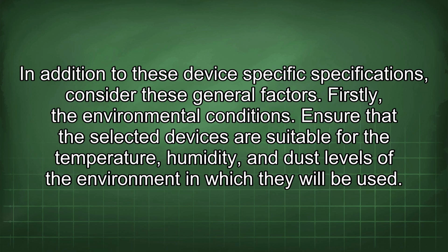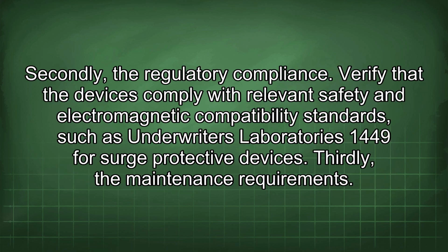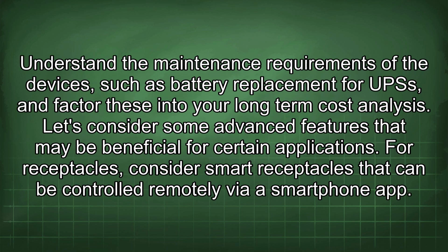Firstly, the environmental conditions. Ensure that the selected devices are suitable for the temperature, humidity, and dust levels of the environment in which they will be used. Secondly, the regulatory compliance. Verify that the devices comply with relevant safety and electromagnetic compatibility standards, such as Underwriters Laboratories 1449 for surge protective devices. Thirdly, the maintenance requirements. Understand the maintenance requirements of the devices, such as battery replacement for UPS, and factor these into your long-term cost analysis.